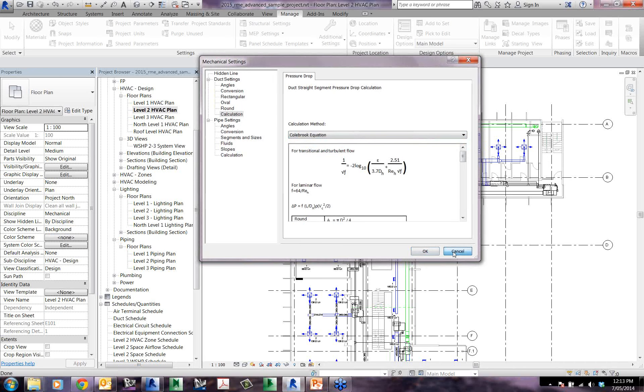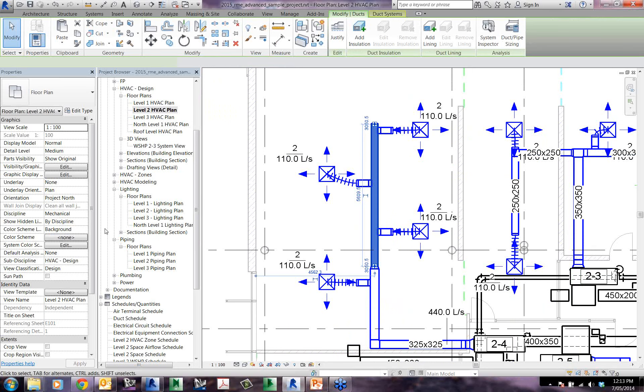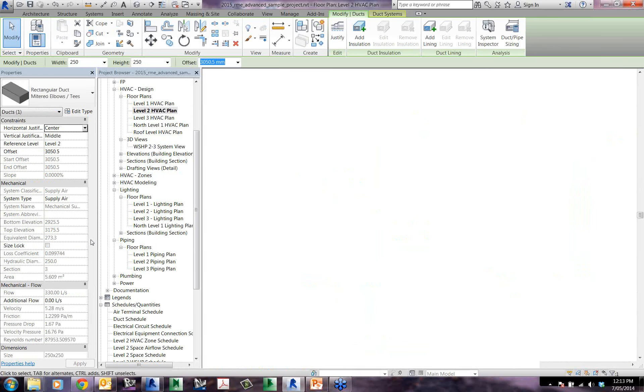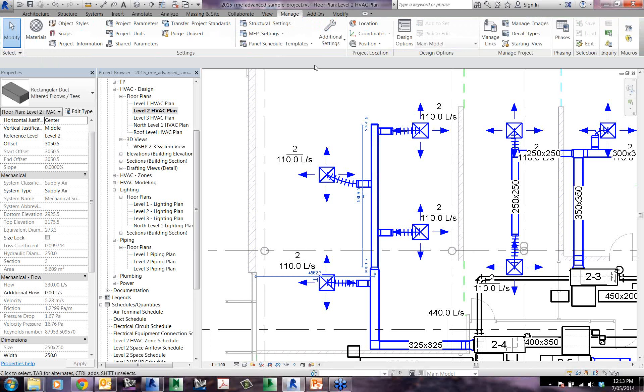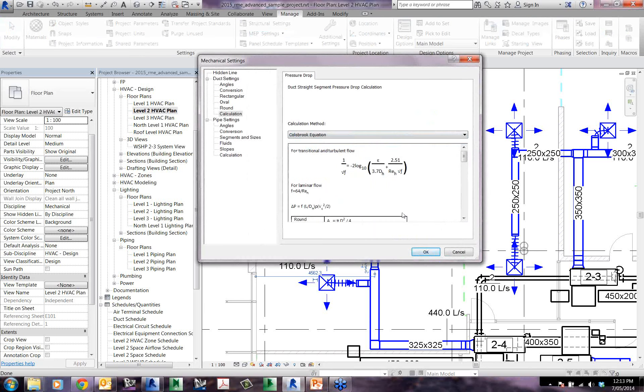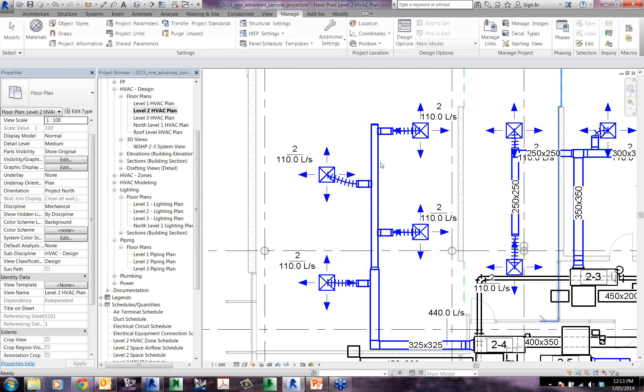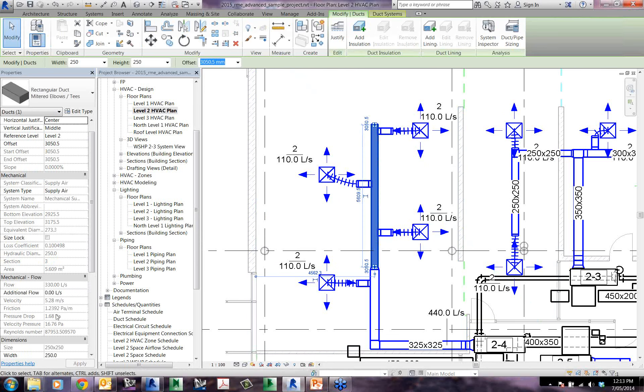If I select a section of duct, I can interrogate the properties on the left-hand side. I have got some parameters regarding the pressure drop. If we come back into the Mechanical Settings and change the calculation to Colebrook as an example — it is setting up the new settings in the background, and you can see it has changed to 1.68 instead of 1.67. So the pressure drop calculations are actively changing depending on which equation is selected.